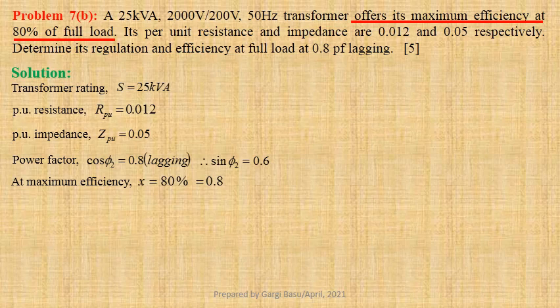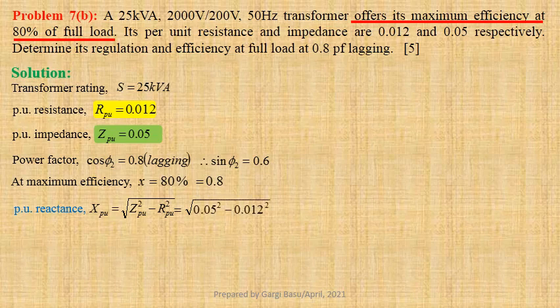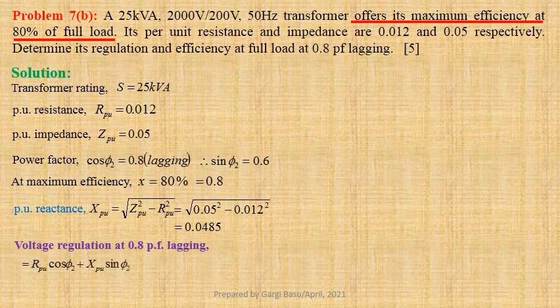Let us first calculate per unit reactance. X per unit equals root over Z per unit square minus R per unit square. Using values we get root over 0.05 square minus 0.012 square, that gives us 0.0485. Now we shall write down the expression for voltage regulation at lagging power factor, which is equal to R per unit cos phi 2 plus X per unit sin phi 2.